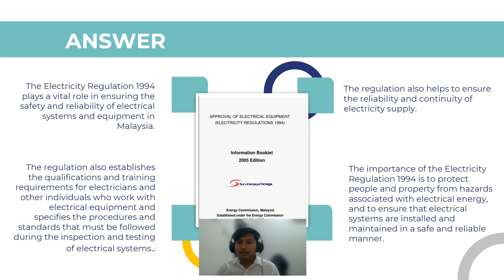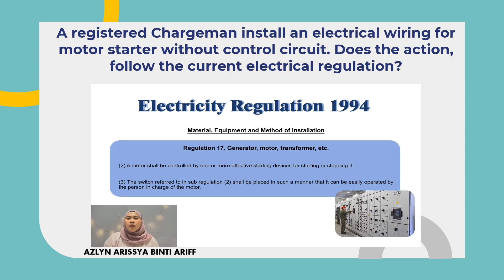Based on the Electricity Regulation 1994, under Material, Equipment and Method of Installation, Regulation 17 on Generator, Motor, Transformer, etc: Sub-regulation 2 states a motor shall be controlled by one or more effective starting devices for starting or stopping it. Sub-regulation 3 states the switch referred to in sub-regulation 2 shall be placed in such a manner that it can be easily operated by the person in charge of the motor.